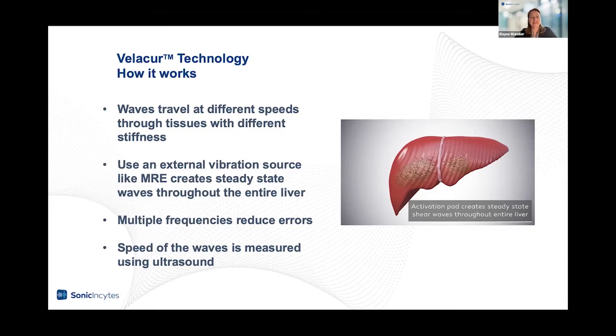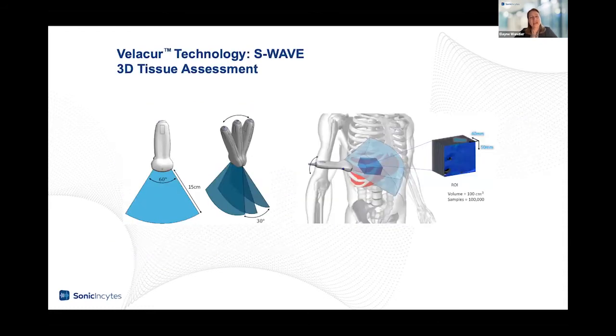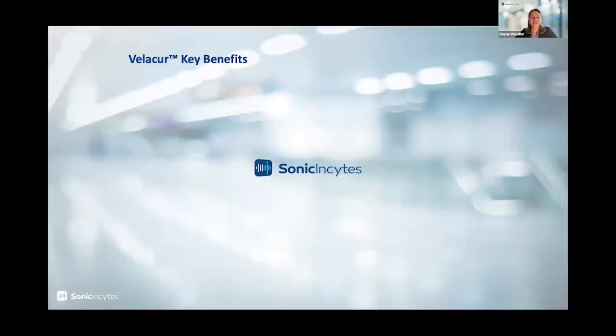The actual ultrasound scan is done with a sweeping motion that allows for a volumetric measurement, hence the three-dimensional tissue sampling. Sampling a big volume of tissue should also contribute to much better accuracy for both measurements of stiffness and fat. A final benefit is that among the entire scan, you can actually choose the best region on which to calculate the measurements with the touch of a finger. So I've explained why Velacur is accurate.